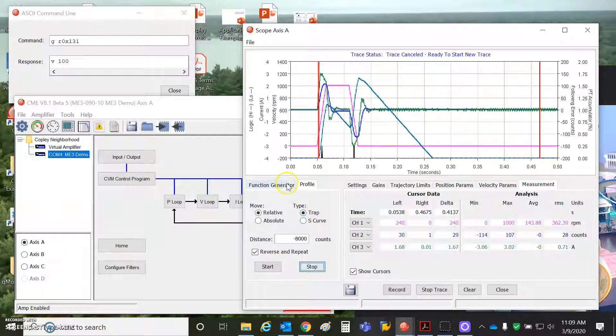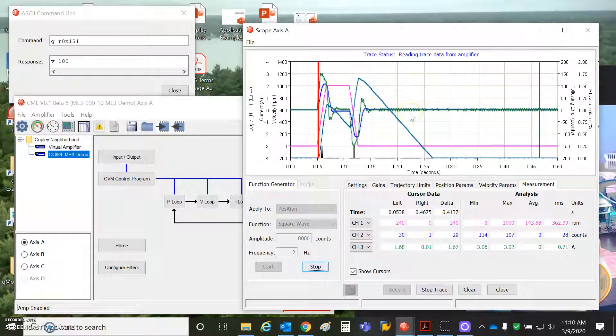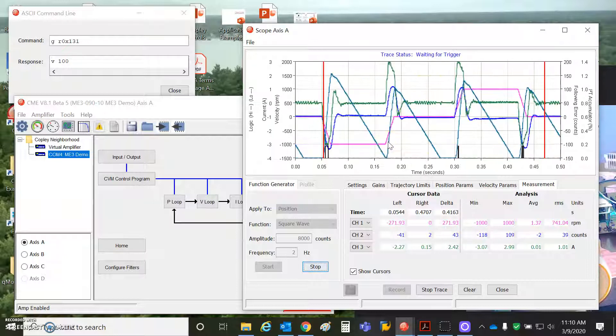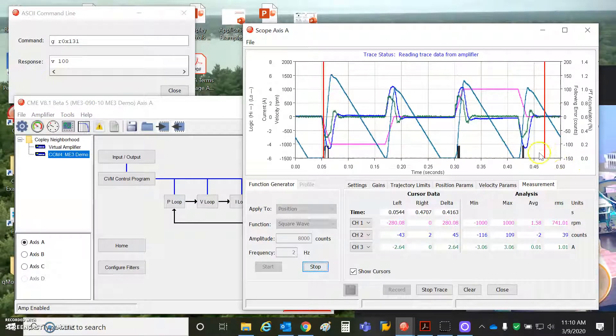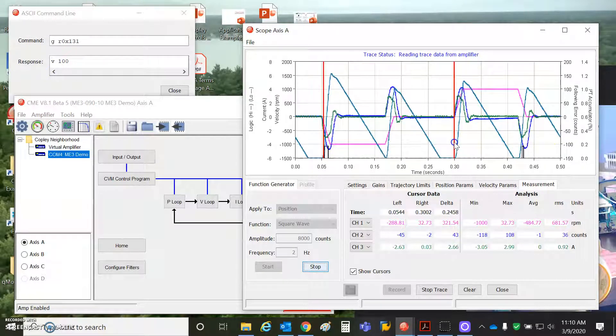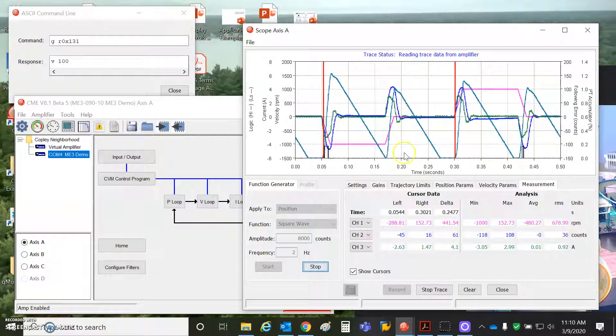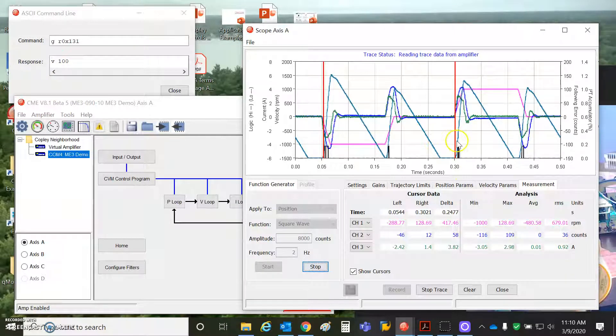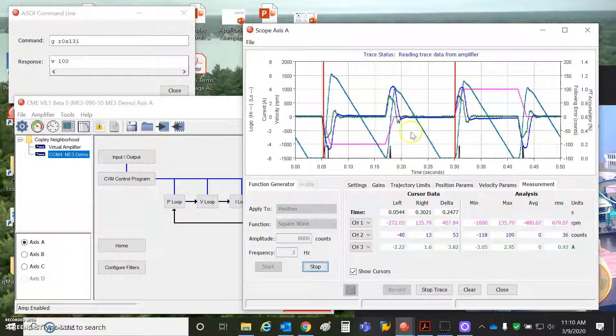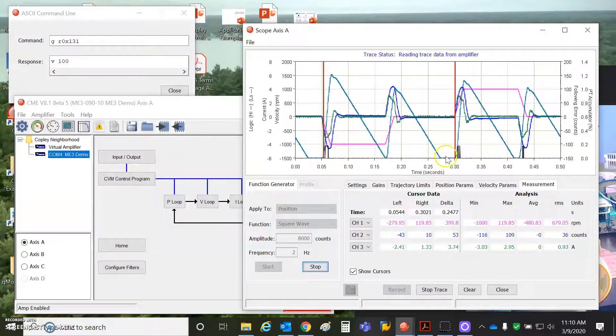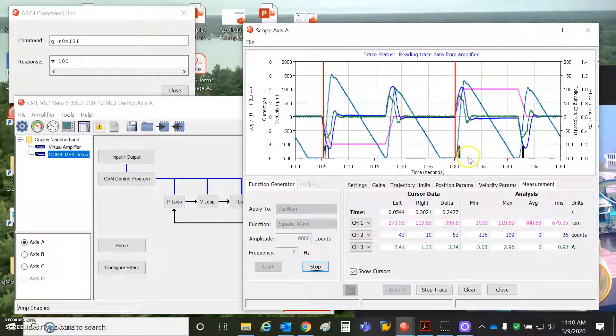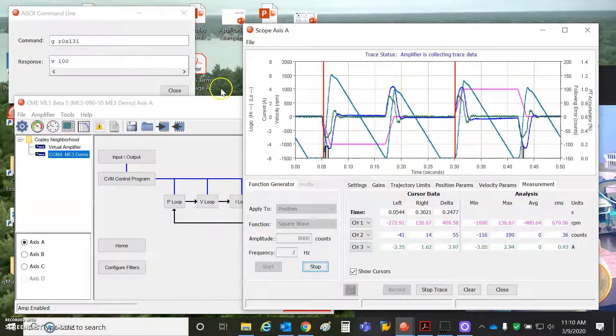So we could do this all day. If I increase the frequency of the moves back and forth, we'll start to see that the I squared T accumulator is getting larger. But you notice it does come back down to zero. So I'm getting kind of near the danger point. So for this period here, it looks good. This is a period of cycling. We could probably do this all day because the I squared T accumulator is not accumulating and we will not get a current limit fault.